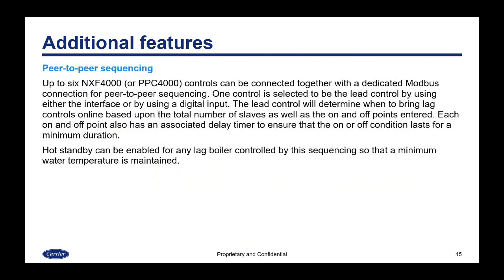Up to 6 NXF4000s, and this can also include PPC4000 controls if your system had both, can be connected together with a dedicated Modbus connection for peer-to-peer sequencing. One control is selected to be the lead control by using either the interface, the keypad, or a digital input. The lead control will determine when to bring lag controls online based upon the total number of slaves as well as the on and off points entered. Each on and off point also has an associated delay timer to ensure that the on or off condition lasts for a minimum amount of time.